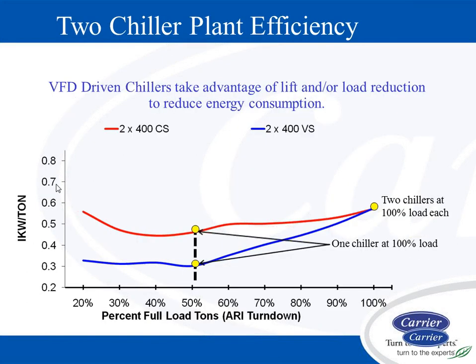So the interesting part here is at the design condition, 2 chillers, the 100% operating point is the same. However, if you look at that 50% point, both the constant speed and the variable speed machine are both operating at the 100% load point. The reason why the kW per ton in blue is less than red is because that blue machine has a variable speed drive on it.